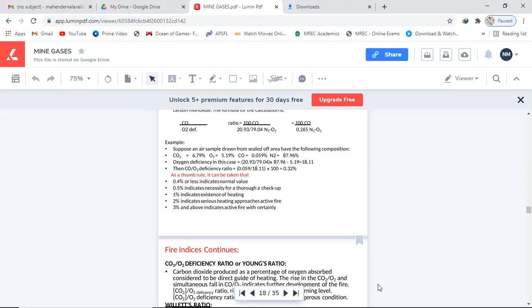And there is some thumb rule. 0.4% or less indicates a normal value, and 0.5% indicates the necessity for a thorough checkup. At 1% it indicates existence of heating, and 2% indicates heating is approaching active fire, and 3% and above indicates active fire. And there are different fire indices, and it still continues.